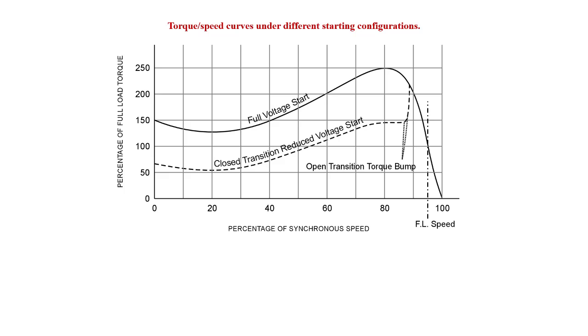All right. So there's a little graph of what I was talking about there. We're going to come back and look at this again. During a full voltage start, it's this one right here. Current would rise up, the torque, and then come back down. We'd operate it down here somewhere at its full load speed and full load torque. With a closed transition starter, like we saw with this part winding, we start it out with one winding. The torque will start to build up, and then when we close the second one, the speed's picking up, it's going to just immediately jump up to match about right here where it would be with a full voltage start. And so we reduce the current on the stator winding by doing this.